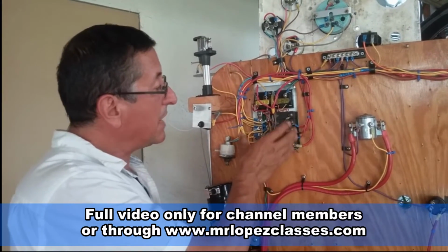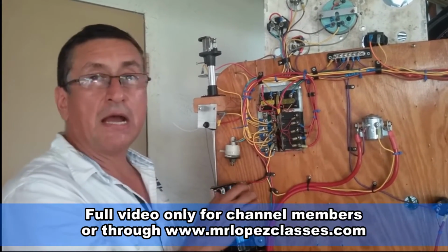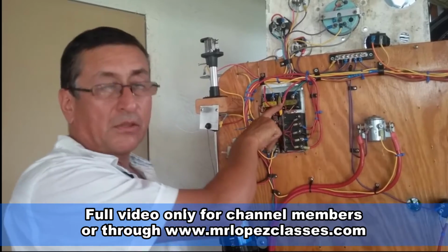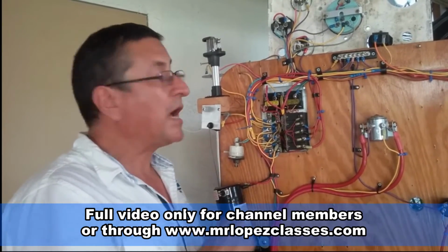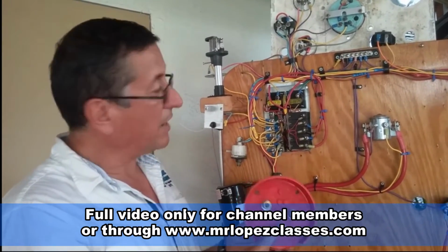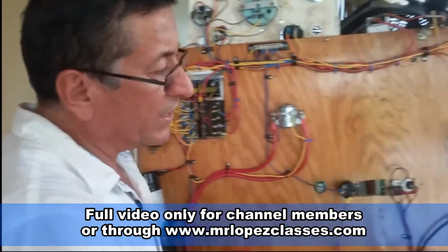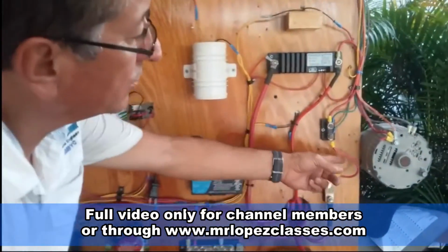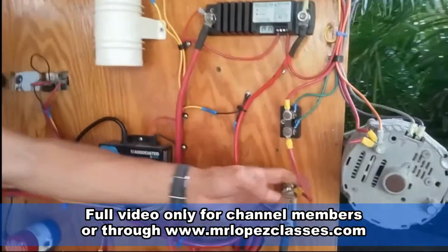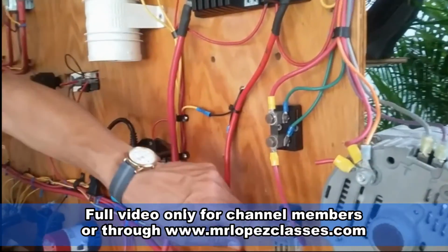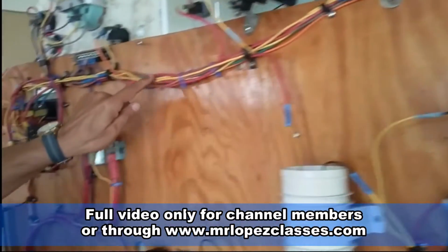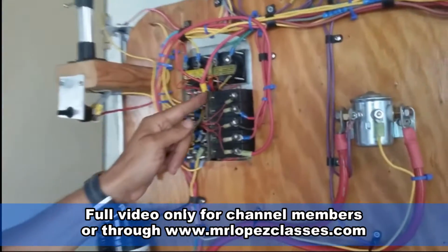This small wire was calculated according to the capacity of this panel. This panel is maximum 25 amps. We use that wire for 30 amps. And from the common, we have two cables. One small wire for the panel, and this is the wire going out into the panel and entering here into the positive bus bar on the panel.